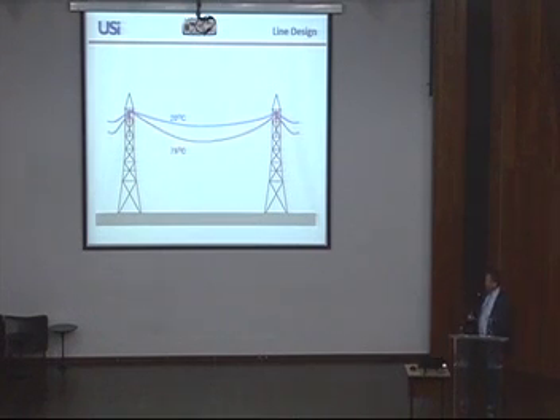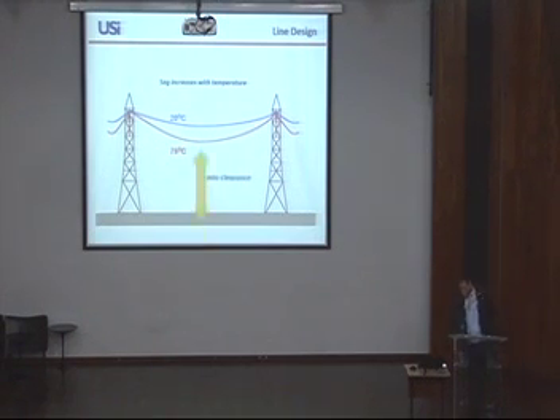And the line is designed in a way that at the maximum operating temperature, here in Brazil, I've learned it's 75 degrees, you are having a minimum clearance. So whatever you do, you have to make sure you are not heating up the conductor more than the maximum temperature. So to have always public safety.